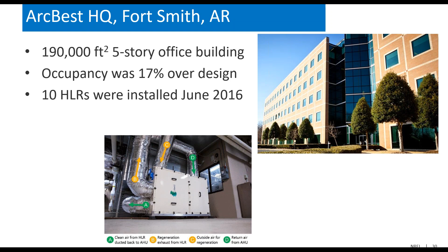And so they were looking at options and what to do. One option was to add additional air handling unit and chiller capacity and boiler capacity. Or the second option was to install the HLR units. So 10 HLRs were installed. And what this did was it enabled them to reduce their outside air during the summer and winter times, reducing that capacity on the HVAC system. We'll talk about the results, but they're able to meet those conditions and still operate effectively without expanding their HVAC system.